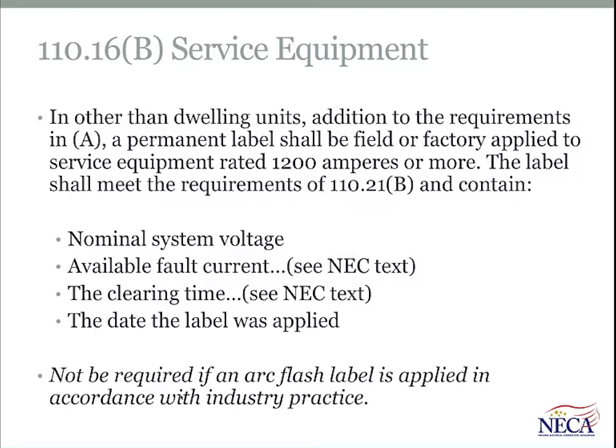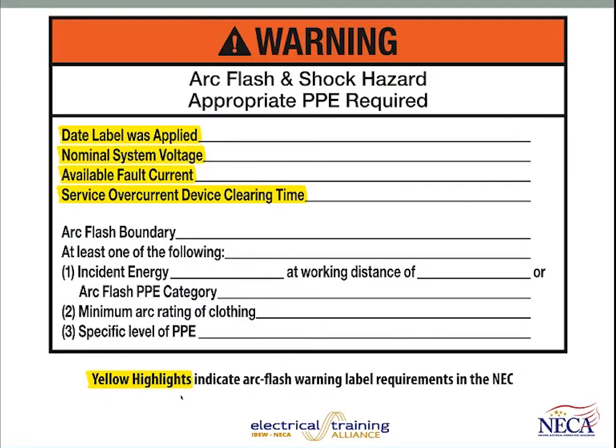The label needs to meet the requirements for durability and the ANSI Z535 criteria. That's what the reference to 110.21(B) gives you. And it also has to contain, in 2017, the nominal system voltage, the available fault current, the clearing time of the service overcurrent device, and the date the label was applied. So these are all installation-related criteria that are now required to be on the arc flash hazard warning label. What we have as an example to show you what the expansion was, in the previous editions of the NEC, everything above the highlighted text is what was required by the NEC, which was just basic information about arc flash hazard warnings.